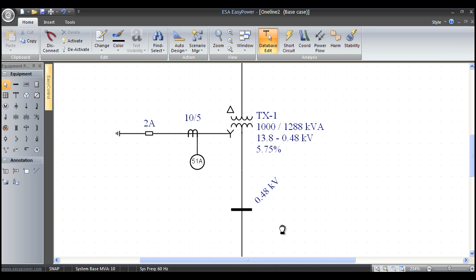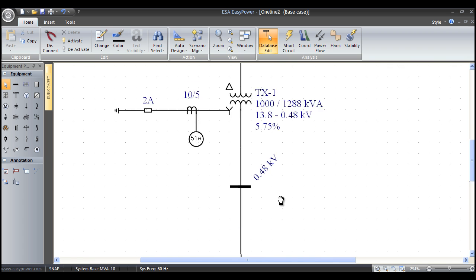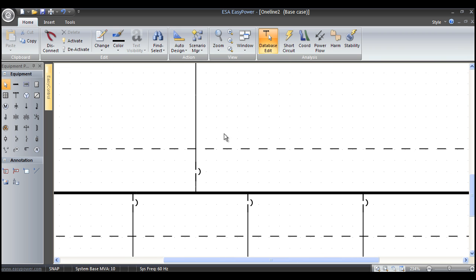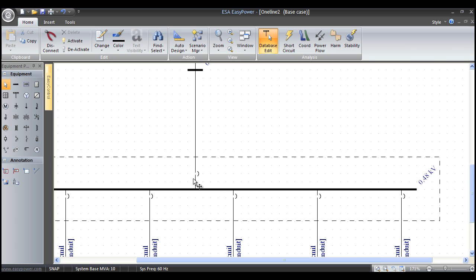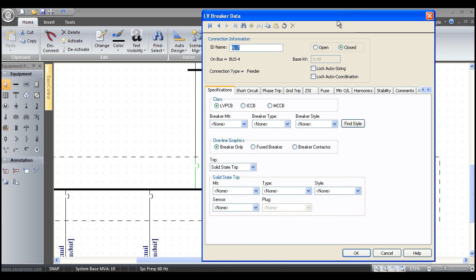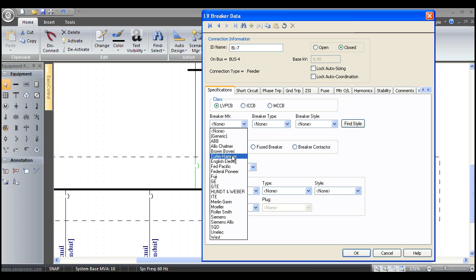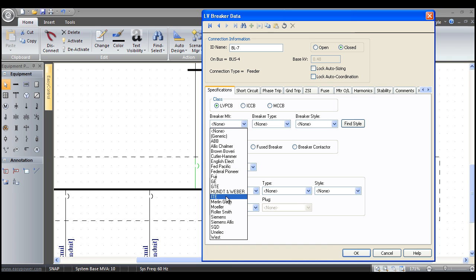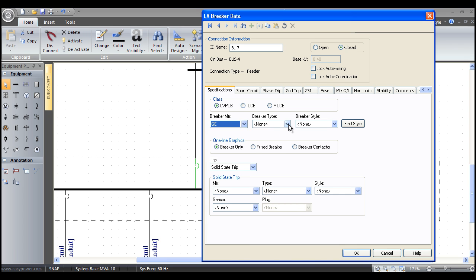Let's press our little roller. I'm going to move the page up to the secondary main breaker of this switchgear lineup. I'm going to left mouse double-click on it and you can see here is the data entry for this breaker. We break low voltage breakers up into the NEMA UL categories of molded case, insulated case, and low voltage power circuit breakers. In this case, we've picked low voltage power circuit breakers. If I select the manufacturer, it will show us all the different manufacturers that make low voltage power circuit breakers and this database goes clear back into the 1940s.